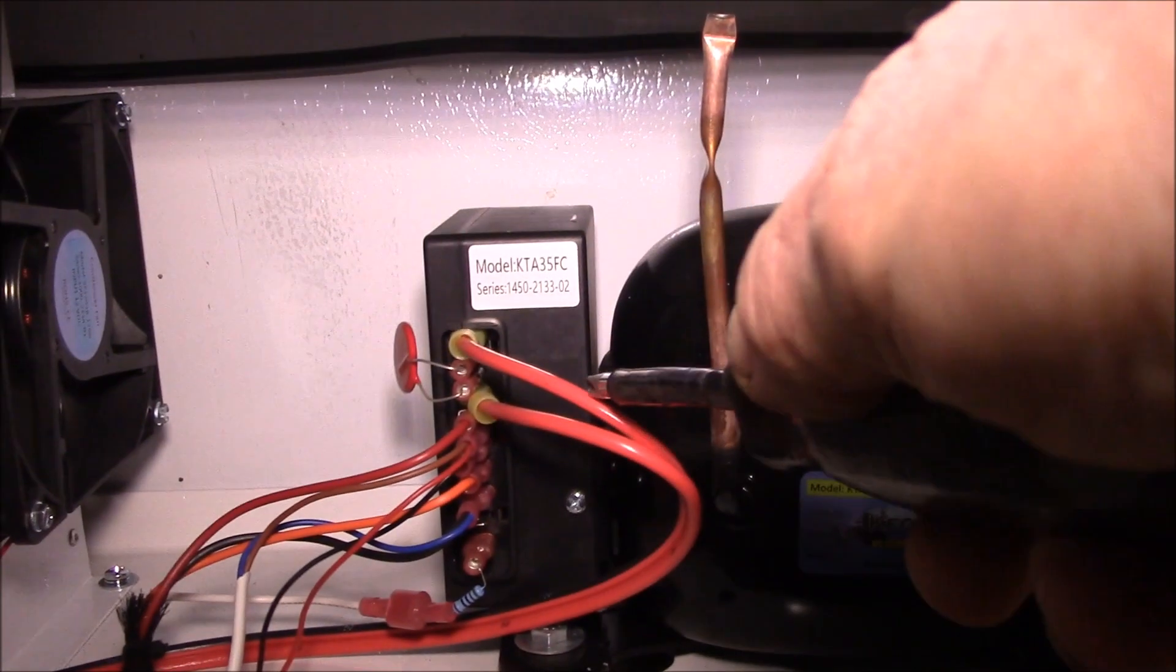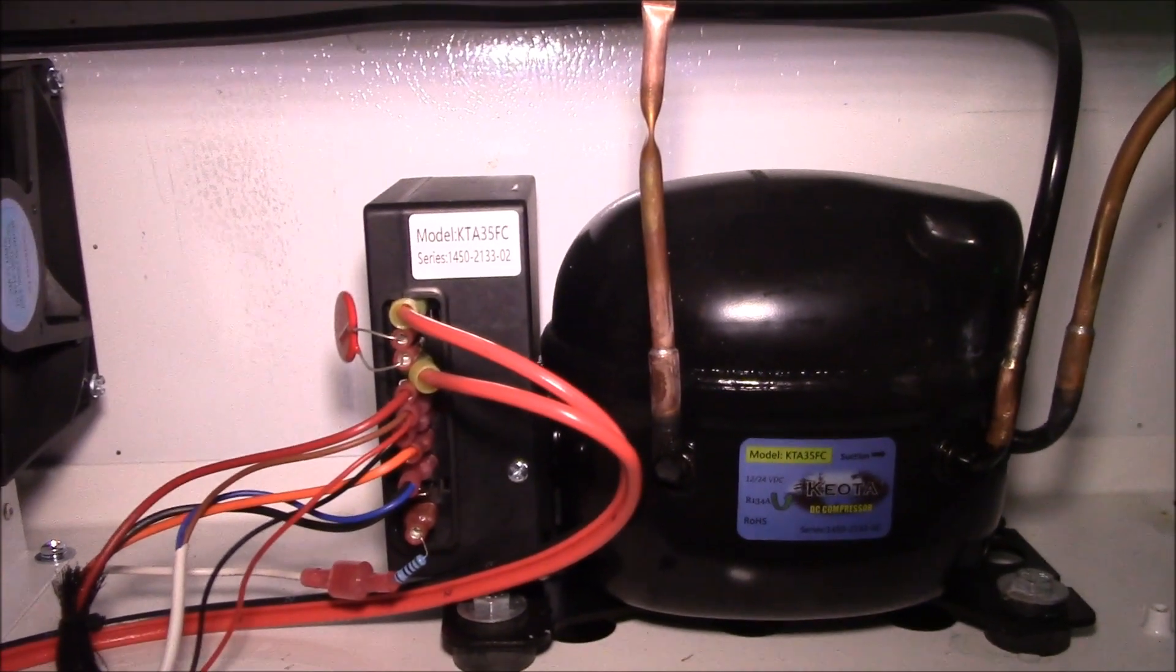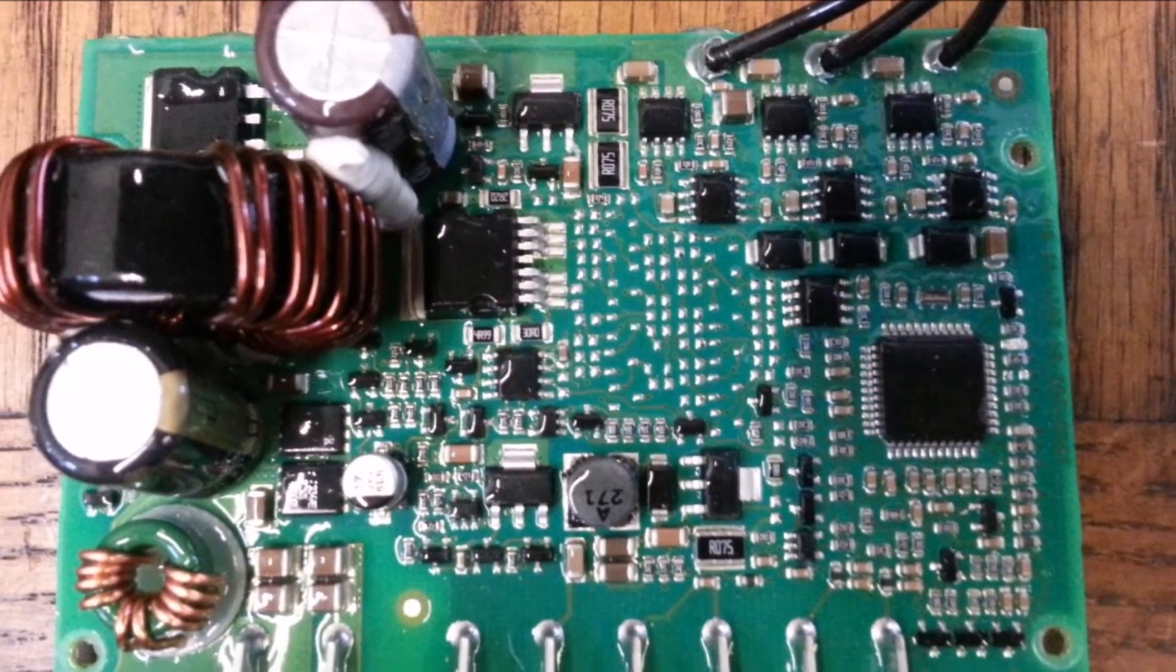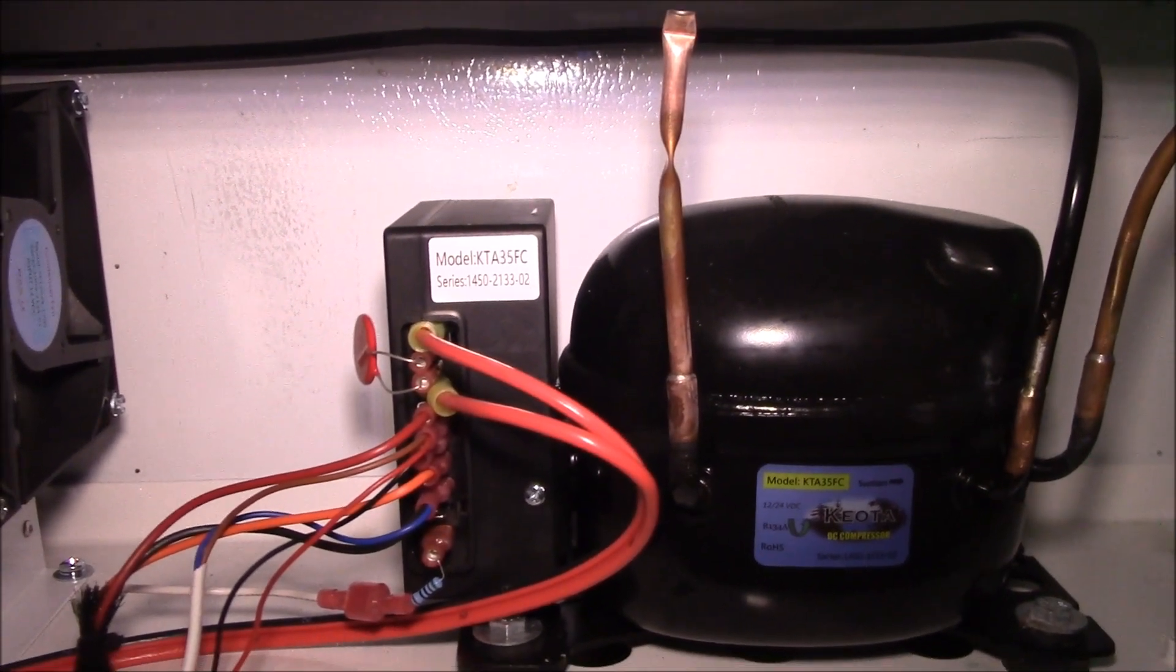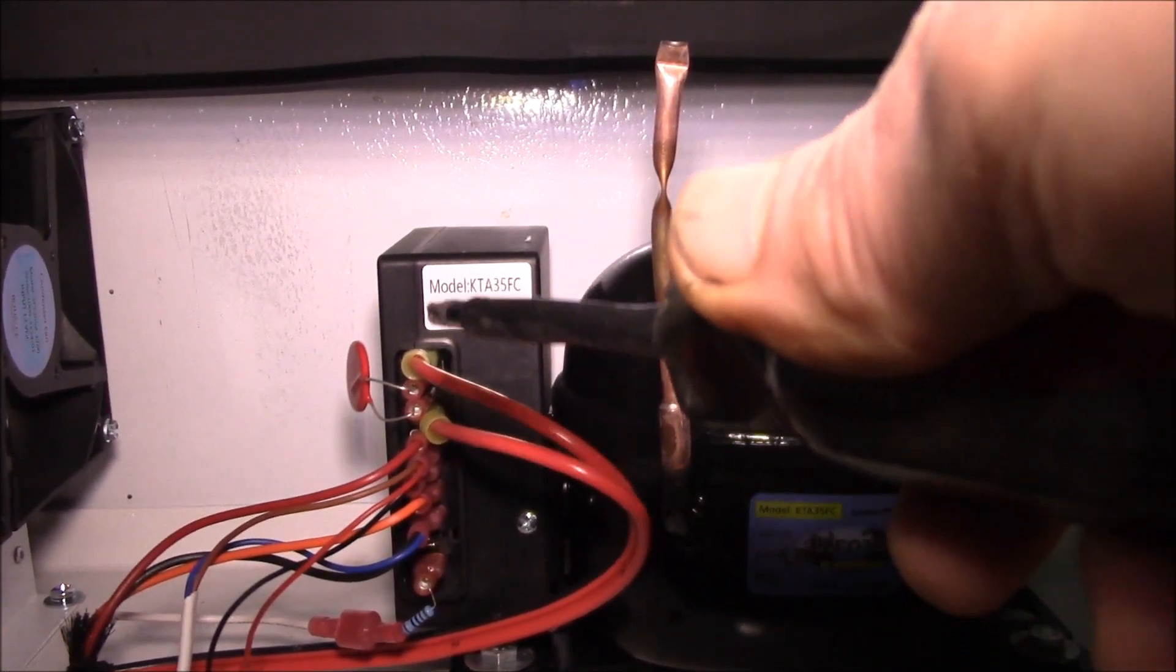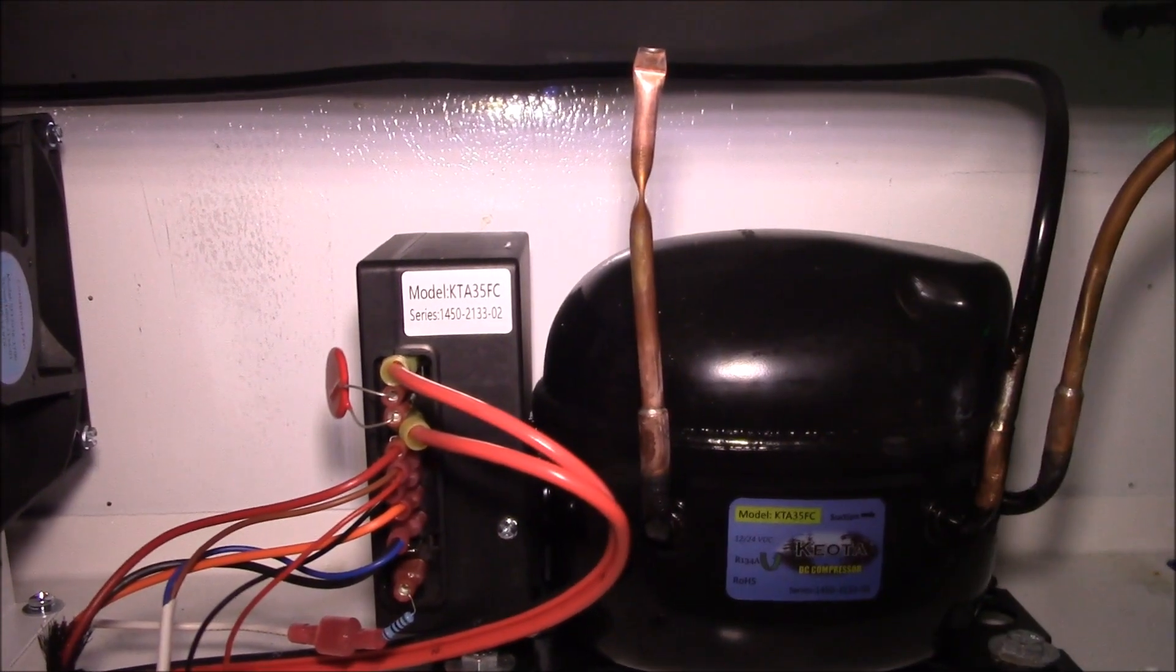This controller here operates that compressor and it's actually a variable speed compressor. This particular controller can run off of 12 or 24 volt DC. They also have a version that has a line and neutral connection on the top for 100 to 240 volt AC input.